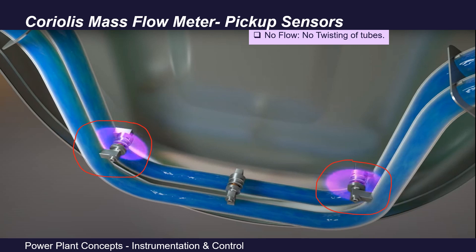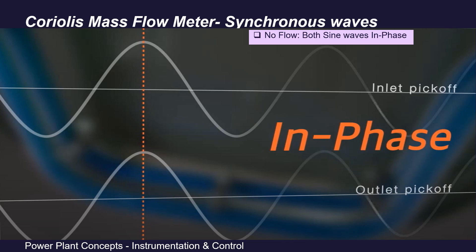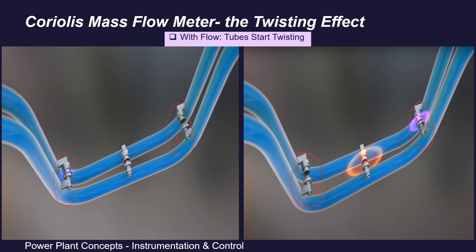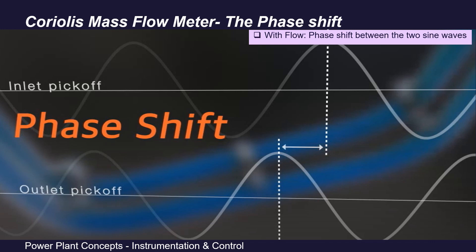The inlet and outlet Coriolis pickup sensors are mounted on the flow tubes as shown in this picture. As the tube oscillates, the voltage generated from each pickup creates a sine wave. The sine wave generated indicates the motion of one tube relative to the other. When there is no flow in the tubes, the inlet and outlet sine waves are in phase — they are in synchronized motion. However, when fluid is flowing through the sensor tubes, Coriolis forces are induced in both flow tubes, causing the flow tubes to twist in opposition to each other. As a result of this twist, the sine waves are shifted in phase and are asynchronous.